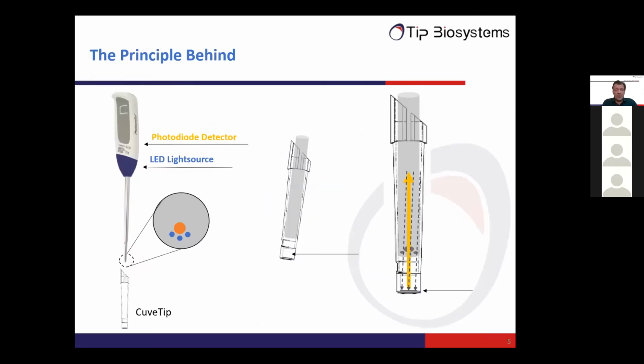So what is the principle behind the work of the Photopette? How does it work? Here on this slide, you see on the left the Photopette device. The Photopette is a fixed wavelength spectrophotometer. In its standard configuration, it has 3 different wavelengths. The light of these 3 different wavelengths is generated by LEDs, and the system is fiber optic based. The light is guided by a fiber optic through this stainless steel stem to the end of the stem. The device also contains a light detector, a photodiode, which collects light and measures the light intensity.